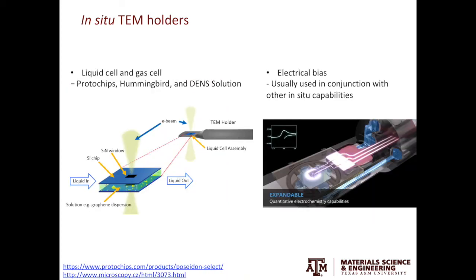You can also use the liquid cell or gas cell in TEM. The thickness of the cell is usually a few hundred nanometers. For the viewing windows, usually is made from the silicon nitride to ensure a good sealing and electron transparency. You then pass the liquid or gas in the cell to observe the chemical reaction in situ. You can also apply electrical bias on the specimen to measure the IV curve. The electrical bias holder is usually used in conjunction with other in-situ capabilities.